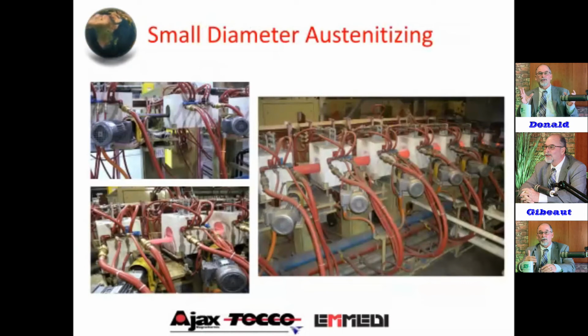Now, this slide makes some people very uncomfortable. If you look at the lower left and the upper left, you'll see a very small diameter tube running through those coils, compared to the right. And everybody that sees that, even competitors, says, man, that's just horrible, your efficiency has to be horrible. Your uniformity, absolutely not. You have to understand the process: the current runs around the circumference of that tube. And if you've got a broader coupling at the top and a real tight one at the bottom, you lose efficiency here, you gain it down here.